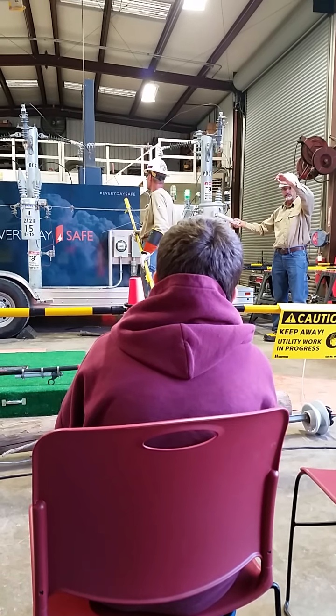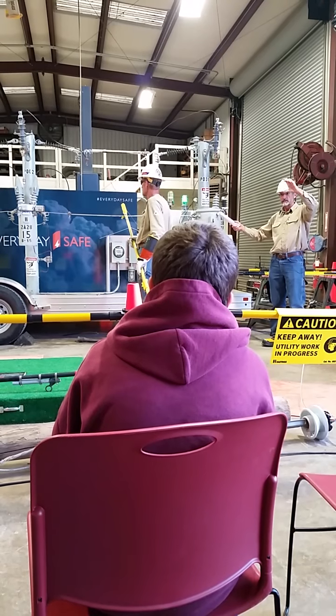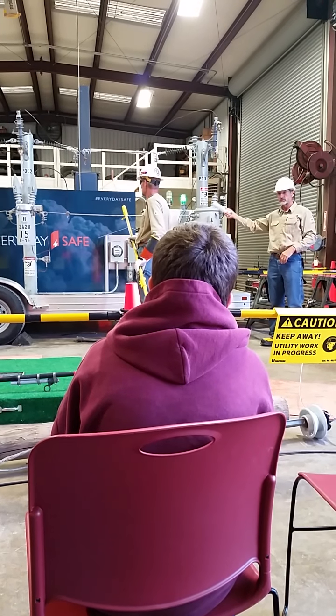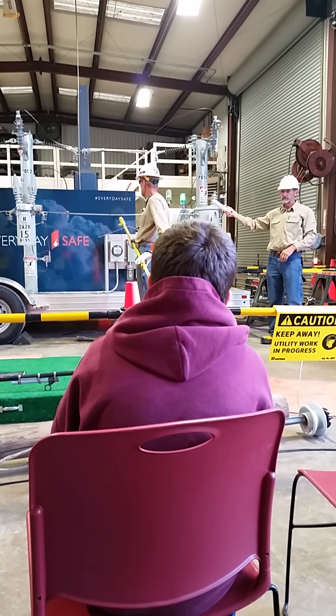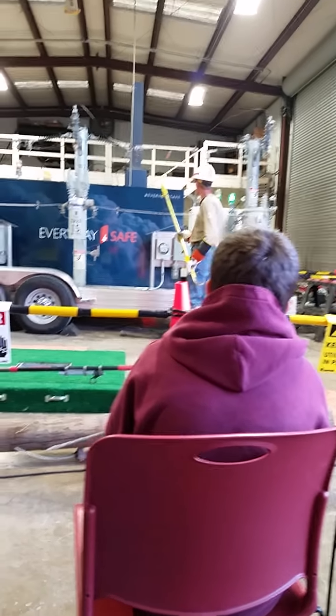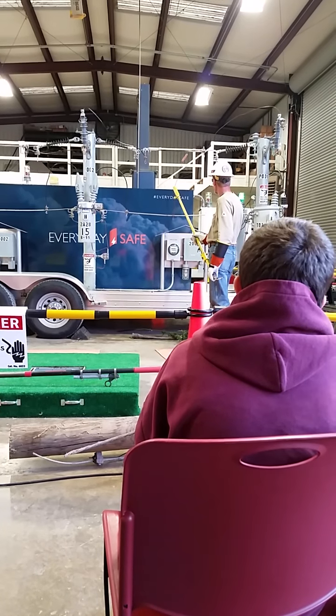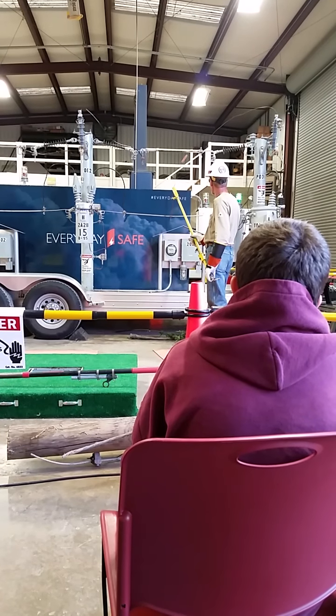A lot of folks will raise a dump bed up and say, oh, it's okay, it's just the bottom wire. If that dump has a better path to ground than that neutral, you're a dead person. And we consider that neutral energized, it's a potential. So Stan, when you're ready, let's show them what will happen to your skin if you make contact with the line. Coming hot.